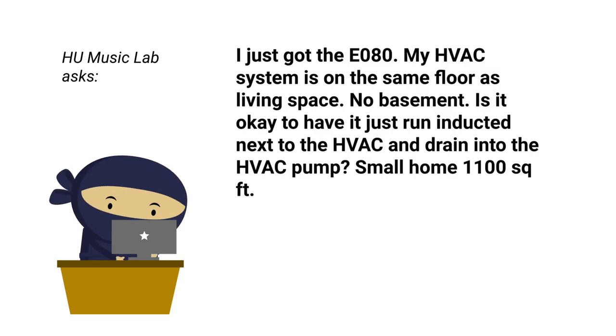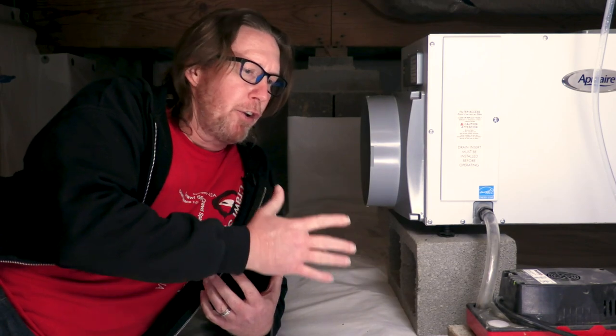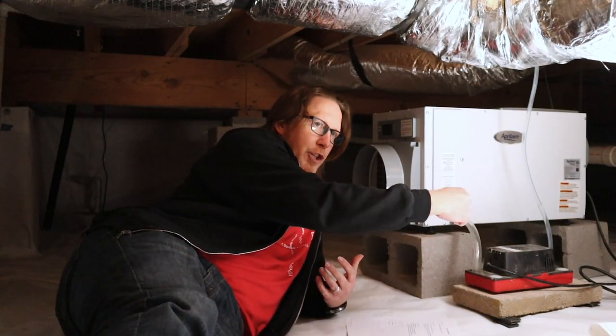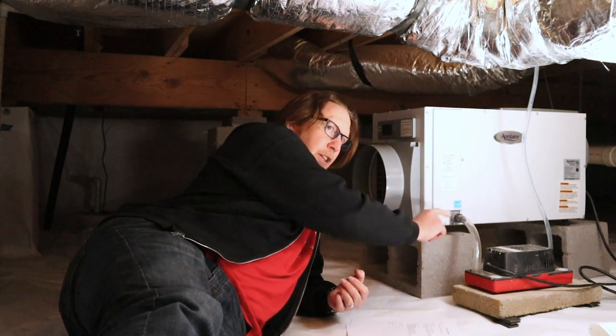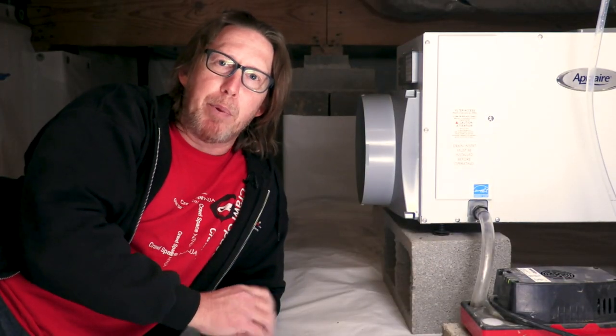So basically what HU Music Lab is describing is a scenario where the heating and air system is right here with a discharge line, and the dehumidifier is right here with its own discharge line — and both of them are discharging into a condensate pump. Is that a good idea? I would say no, it is not a good idea.